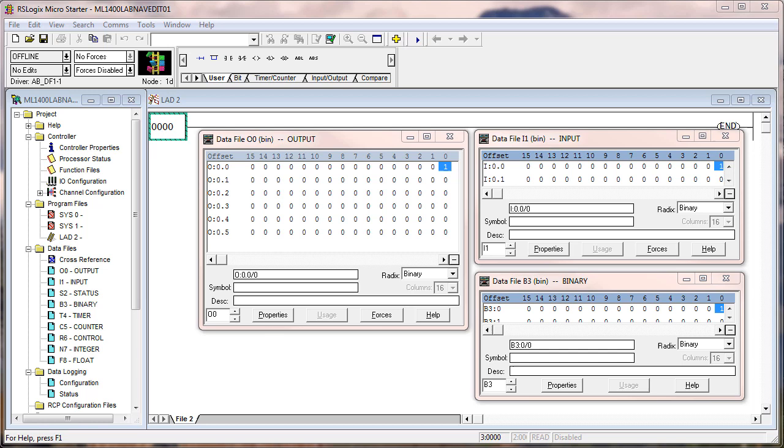And then you need internal data. In other words, you need bits that you can control with logic that are individual little decision-making pieces, like all the safeties are met, all the switches are turned off, all the sensors are seeing the cylinders back in the right position, that kind of stuff. So these three files right here, input, output, and internal bits that aren't connected to I/O, are the most used in PLC programming land.